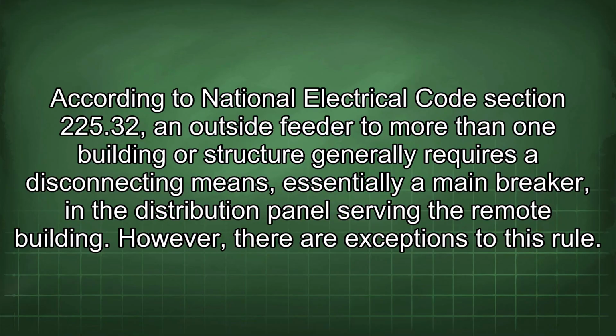According to National Electrical Code Section 225.32, an outside feeder to more than one building or structure generally requires a disconnecting means, essentially a main breaker, in the distribution panel serving the remote building. However, there are exceptions to this rule.